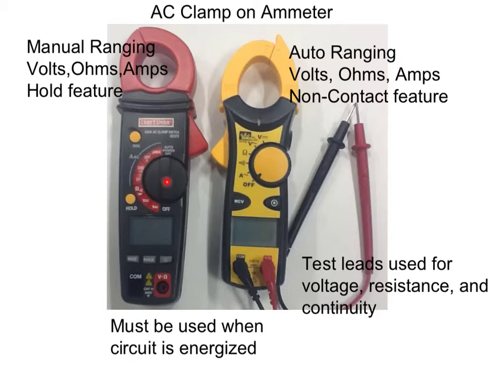Again, this one has the dial range, and so you're going to have to adjust to the particular scale. Typically when you're using a manual ranging meter, you always start at the highest scale and then you begin to work your way down until you find your lowest current value, and you measure it, and that way you can make sure you have the most accurate measurement that you can make.